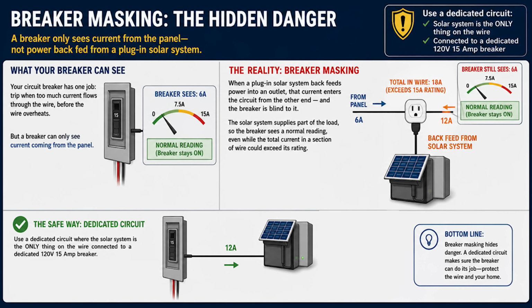The reason this is important: your circuit breaker's one main job is to trip when too much current flows through the wire before it overheats and causes a problem. But as I understand it, a breaker can only see current coming from the panel. When a plug-in solar system backfeeds power into an outlet, the current enters the circuit from the other end, and the breaker is blind to it. The solar system supplies part of the load, so the breaker sees a normal reading even when the total current in a section of wire could be exceeding its rating. This is called breaker masking. So the best way to handle this is to have a dedicated circuit breaker with a dedicated outlet connected only to that breaker—that's where you should get an electrician involved.